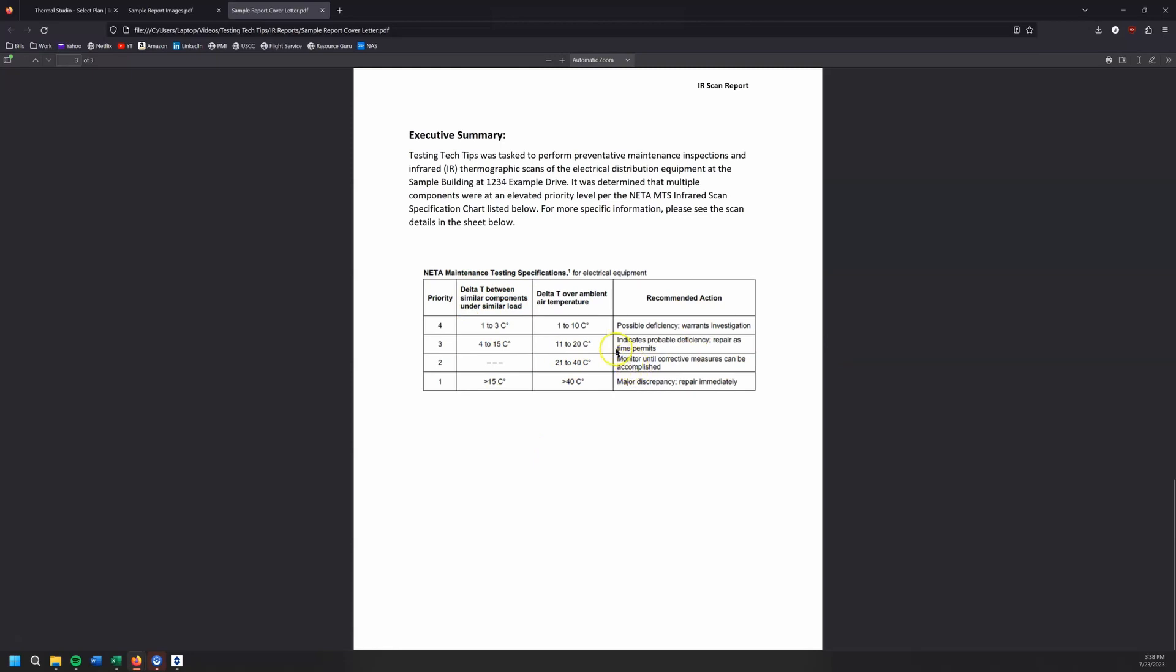So this says, hey, if I've got a delta T between similar components under a load, that's a one to three C. Okay. It's possible deficiency four to 15 C, a probable deficiency. We should really address this pretty soon. Over 15 C between similar loads, like we need to fix this right away and then delta T over ambient. And I found these temperatures, sort of, it's really all over the place. It depends what I'm looking at.